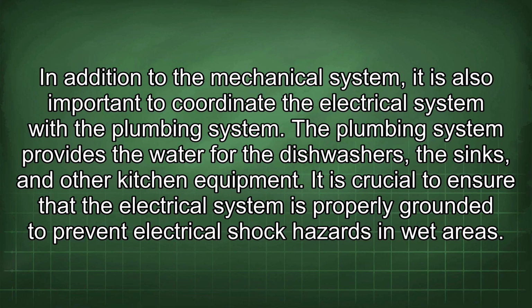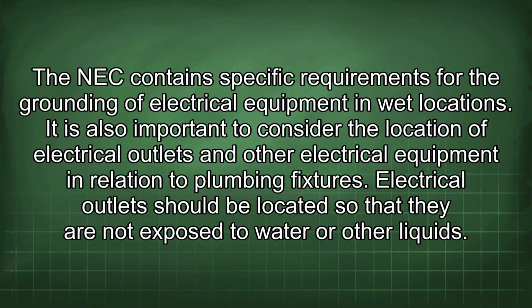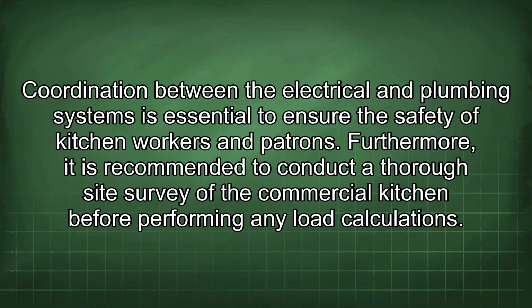In addition to the mechanical system, it is also important to coordinate the electrical system with the plumbing system. The plumbing system provides the water for the dishwashers, the sinks, and other kitchen equipment. It is crucial to ensure that the electrical system is properly grounded to prevent electrical shock hazards in wet areas. The NEC contains specific requirements for the grounding of electrical equipment in wet locations. It is also important to consider the location of electrical outlets and other electrical equipment in relation to plumbing fixtures. The electrical outlets should be located so that they are not exposed to water or other liquids. Coordination between the electrical and plumbing systems is essential to ensure the safety of kitchen workers and patrons.